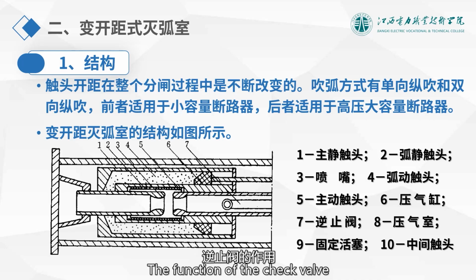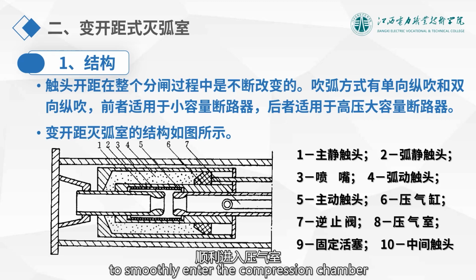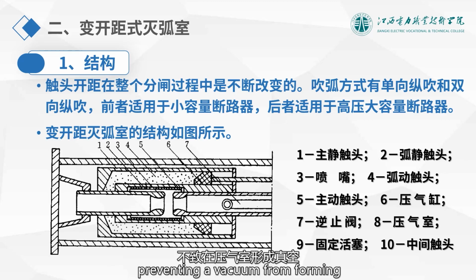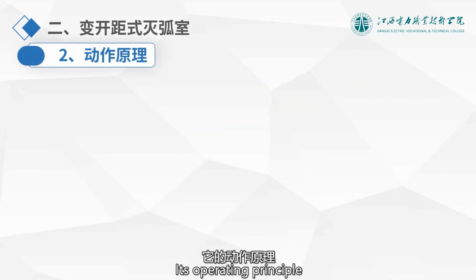The function of the check valve is to ensure that during the opening process, the gas in the compression chamber is concentrated to blow the arc towards the nozzle. During the closing process, the check valve opens, allowing external sulfur hexafluoride to smoothly enter the compression chamber, preventing a vacuum from forming in the compression chamber. Its operating principle is as follows.